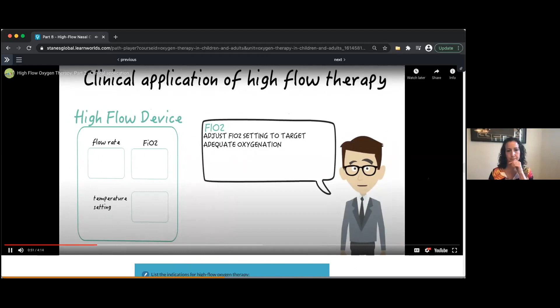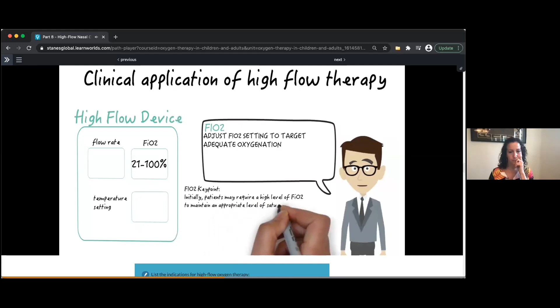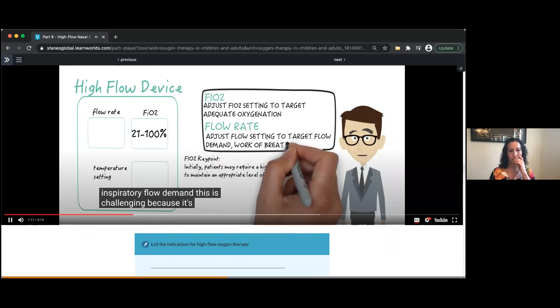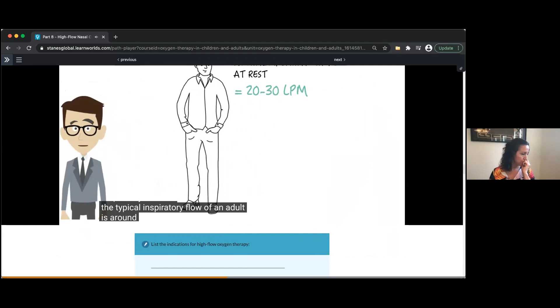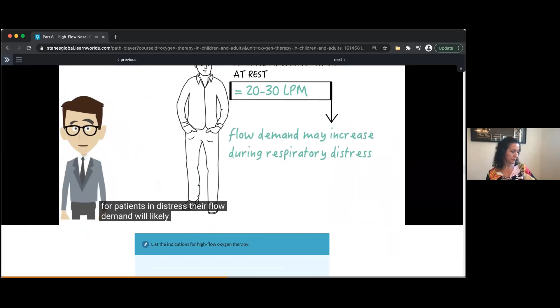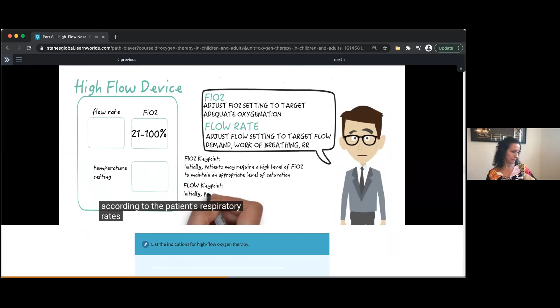Let's look at FiO2 first. This is typically adjusted to maintain adequate oxygenation. The FiO2 can be set from a level of 21% to a level of 100%. Usually, patients in acute respiratory distress who are on high flow may initially require a high level of FiO2 to maintain an appropriate saturation. Next is the flow setting. The flow is usually set to try to meet or exceed the patient's inspiratory flow demand. This is challenging because it's difficult to determine what the patient's inspiratory flow is. We learned in the previous video that at rest, when the patient isn't in respiratory distress, the typical inspiratory flow of an adult is around 20 to 30 liters per minute. But for patients in distress, their flow demand will likely be higher. So clinicians often titrate the flow according to the patient's respiratory rate. In other words, the faster the patient is breathing, the more flow they'll probably need.